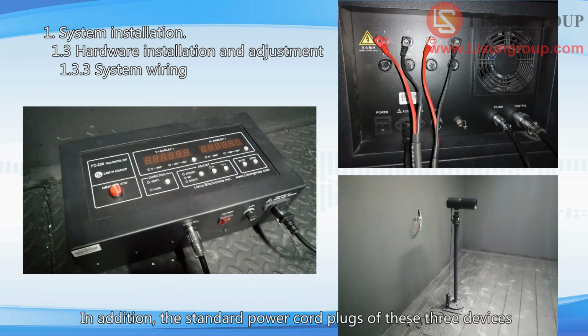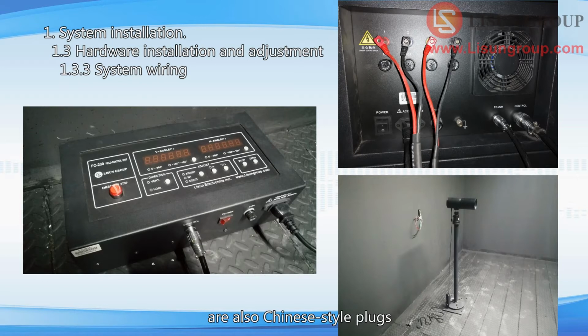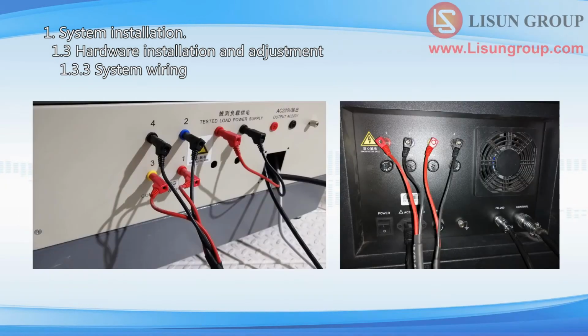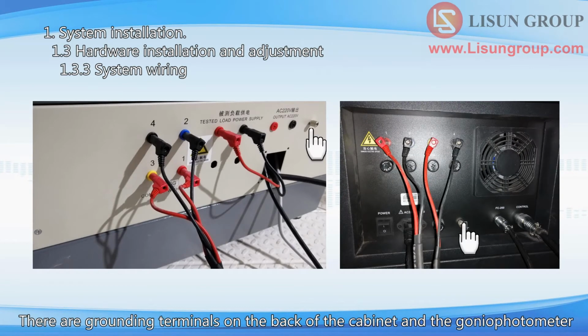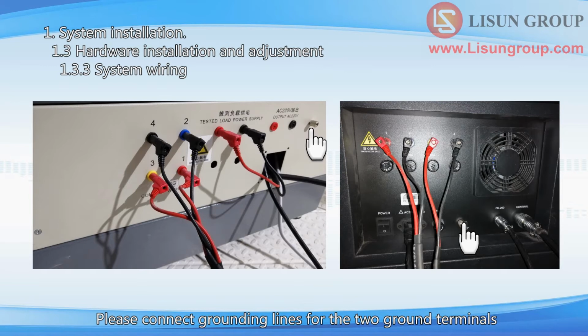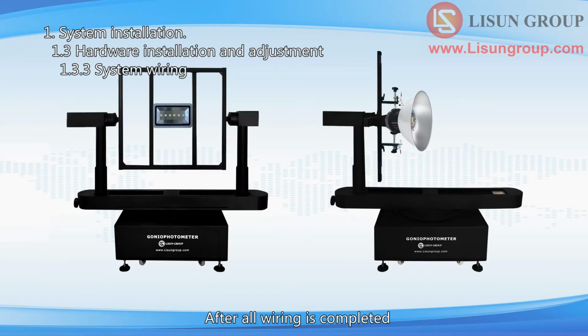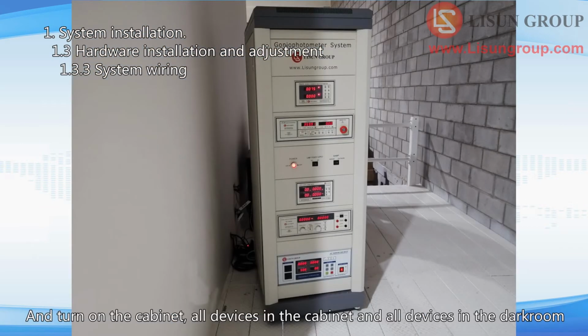In addition, the standard power cord plugs of these 3 devices are also Chinese-style plugs. Please prepare suitable adapters if necessary. There are grounding terminals on the back of the cabinet and the goniophotometer. Please connect grounding lines for the 2 ground terminals. After all wiring is completed, connect the system to 220V 50 Hz power supply. And turn on the cabinet, all devices in the cabinet and all devices in the darkroom.